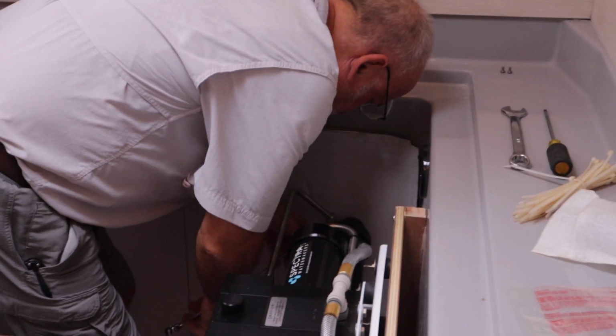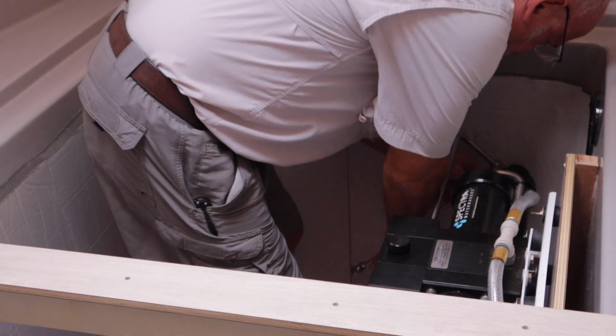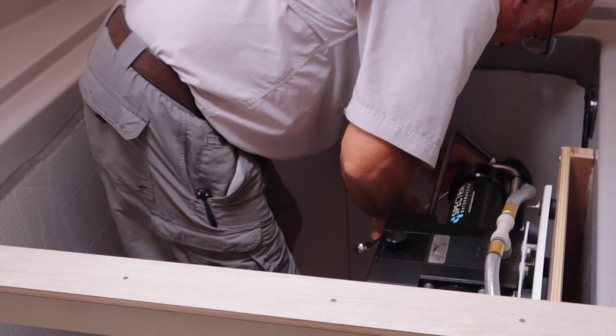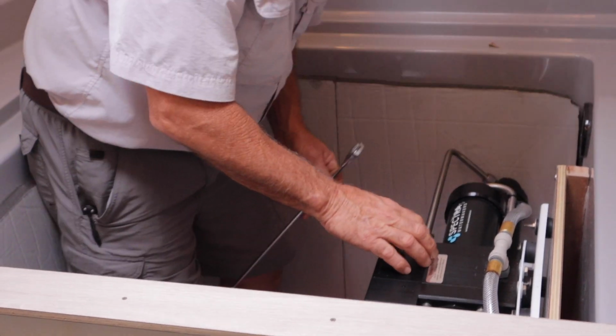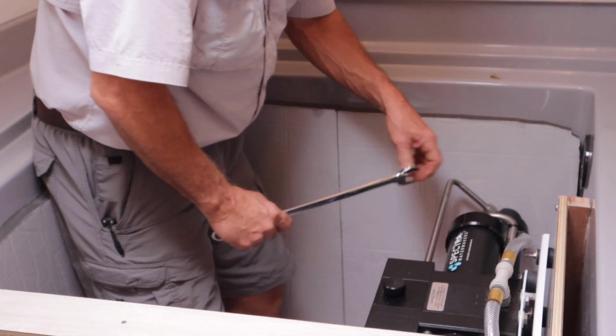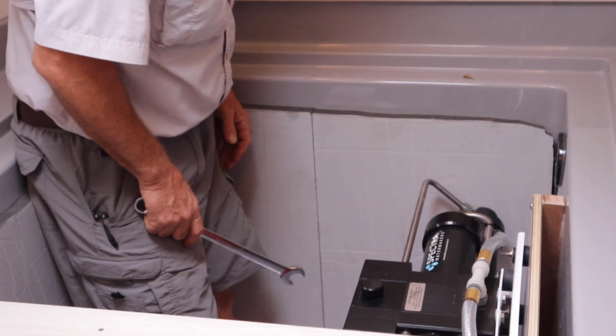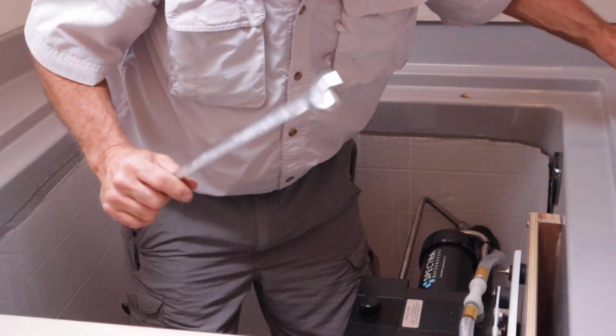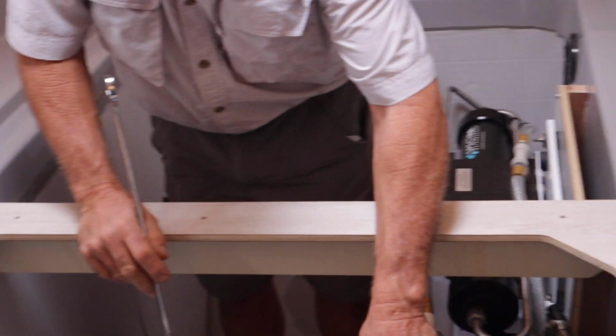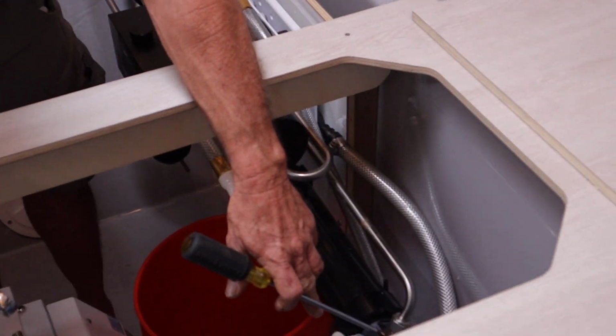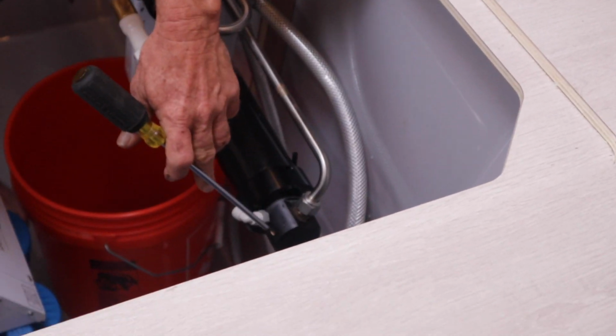If this system leaks, okay, what we don't do is just start tightening things down to stop the leak, especially anything metallic that touches anything black like this. If this leaks anywhere here, let me know. What would be nice is if you could take a picture and say, JT, it's leaking from here, from here, or here, and I'll tell you how to fix it. Okay. This is plastic. This whole pump is plastic.